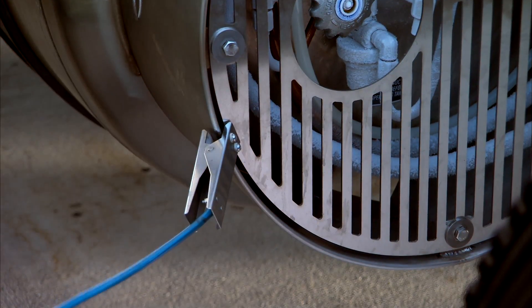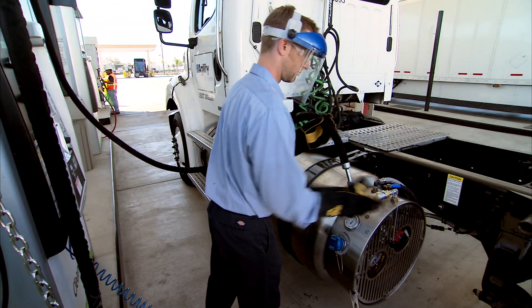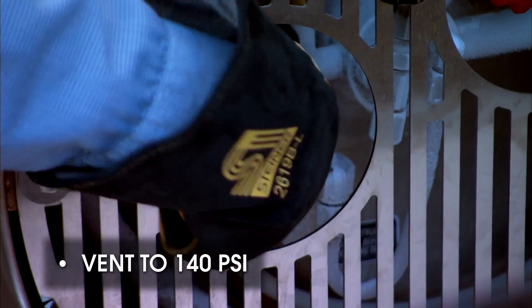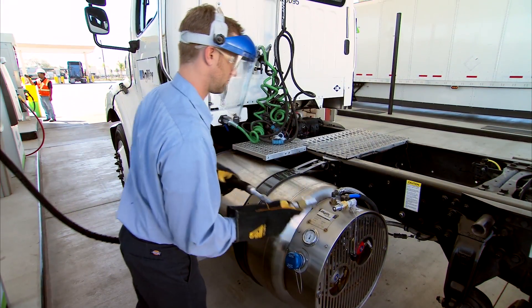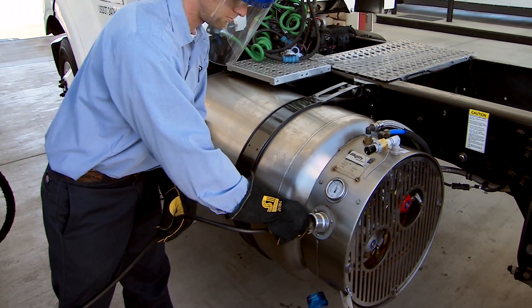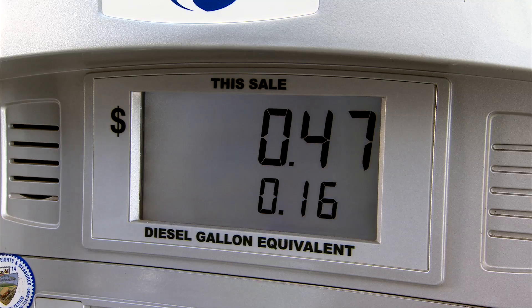Connect the ground cable from the pump to the vehicle tank. If pressure inside the tank exceeds 150 psi, clean the vent connector with compressed air and connect the vent hose from the filling station to the tank vent connector. Open the gray-handled vent valve on each tank and allow the system to vent down to about 140 psi. Once achieved, close the vent valves and return the vent hose to the filling station. Never leave the vent hose connected with the vent valve open during fueling, or fuel may simply circulate into and out of the tank. Use compressed air to clean the fill receptacle and nozzle, then insert the nozzle, lock it in place, and begin fueling. The pump will shut off automatically when the fill is complete. The single receptacle will fill all tanks.